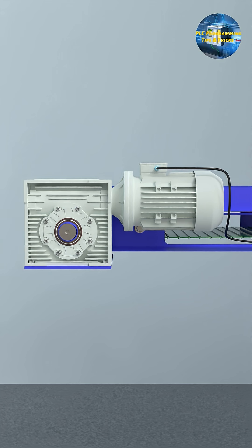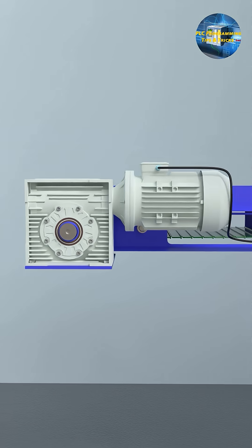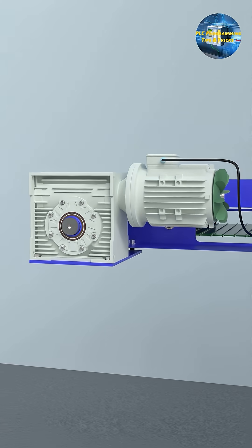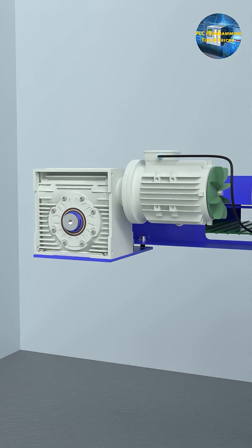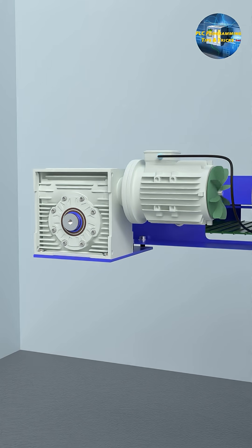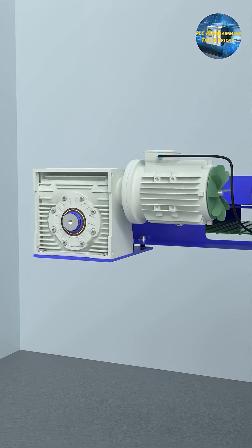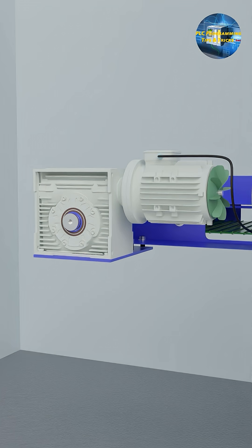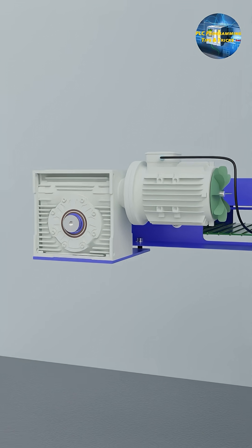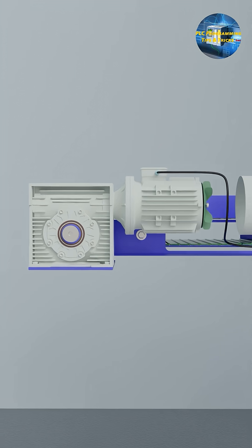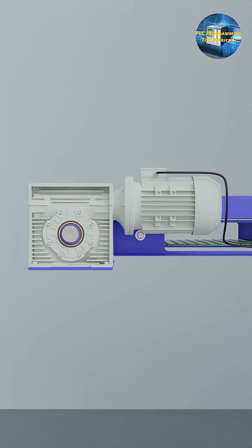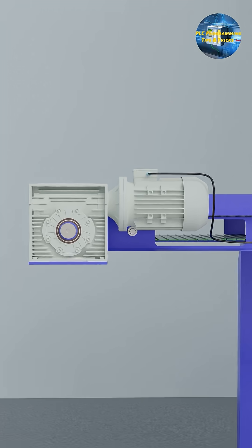For this, we will open the back cover of the motor. If you try to rotate the motor shaft by grabbing the motor fan and you find it really difficult to move the motor shaft or it is not moving at all, this means that there is something wrong with the mechanical components of the system.